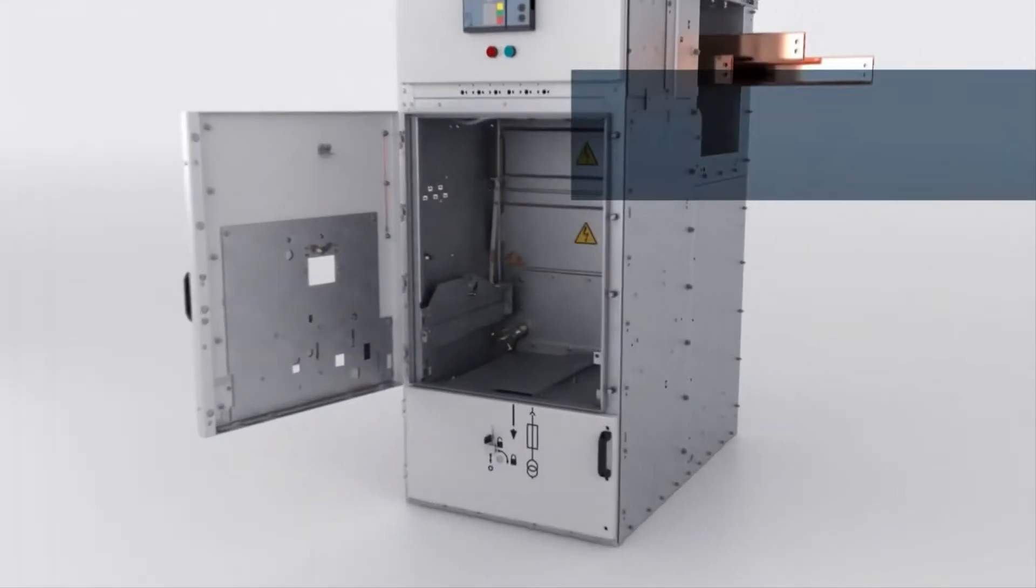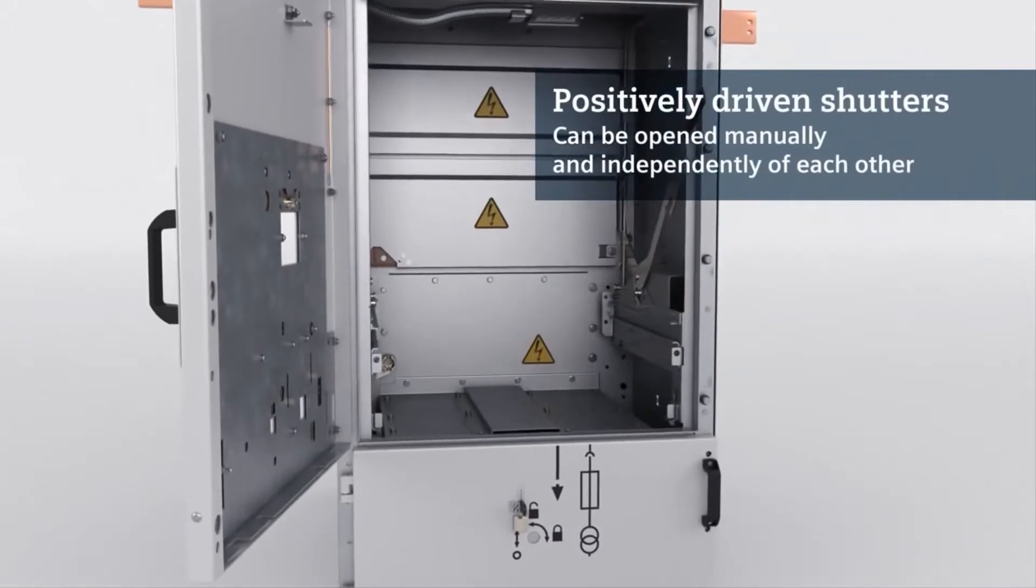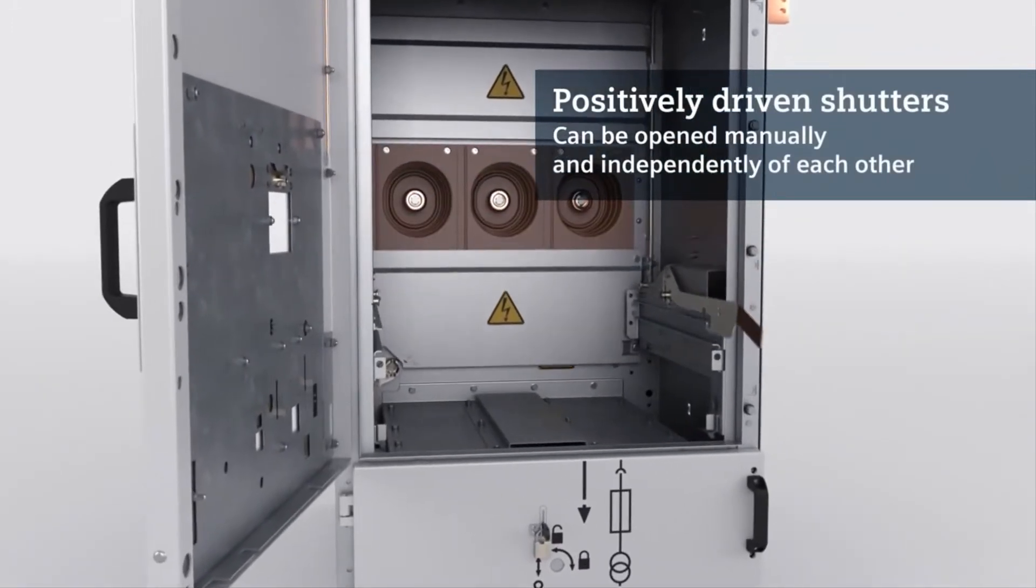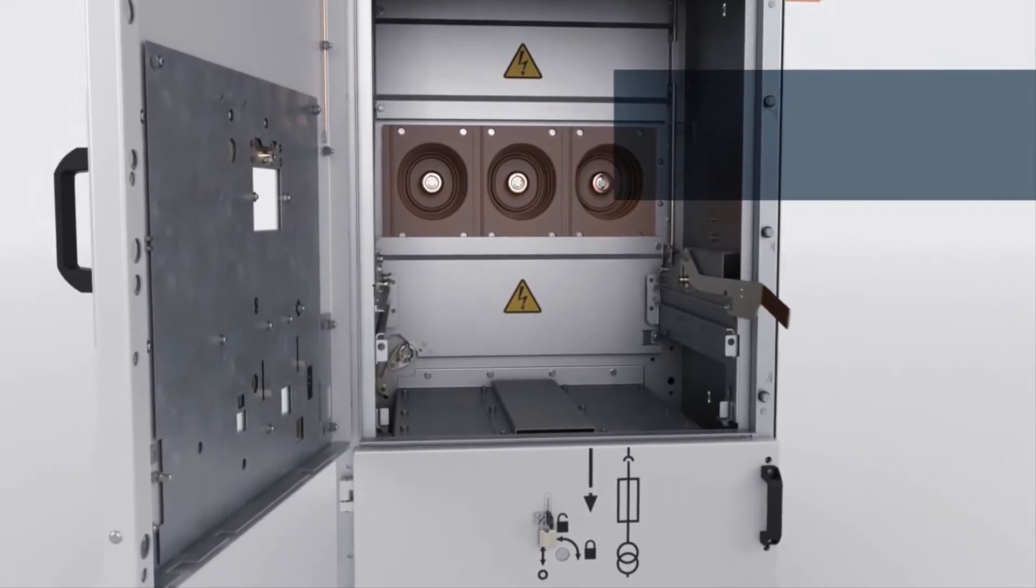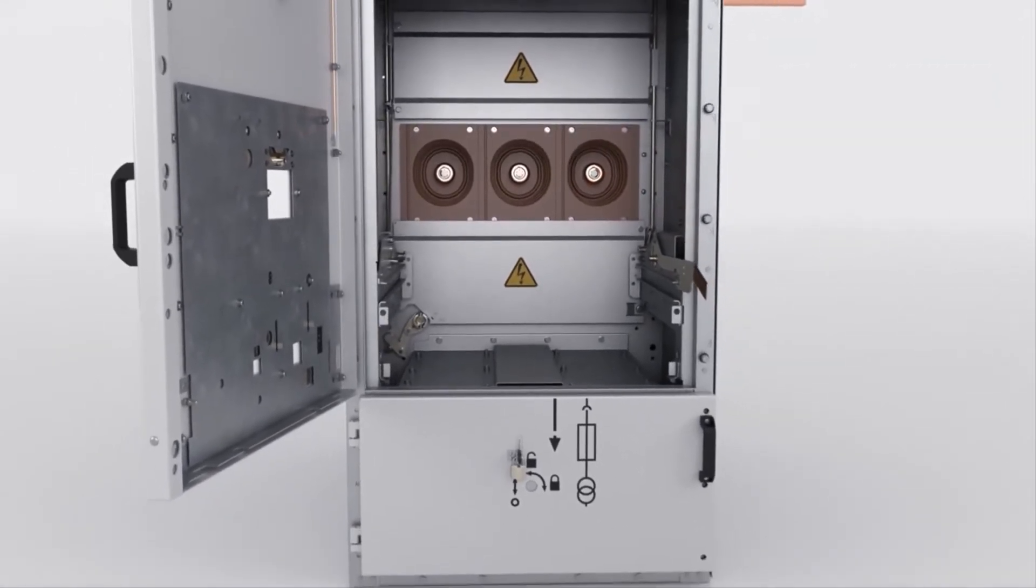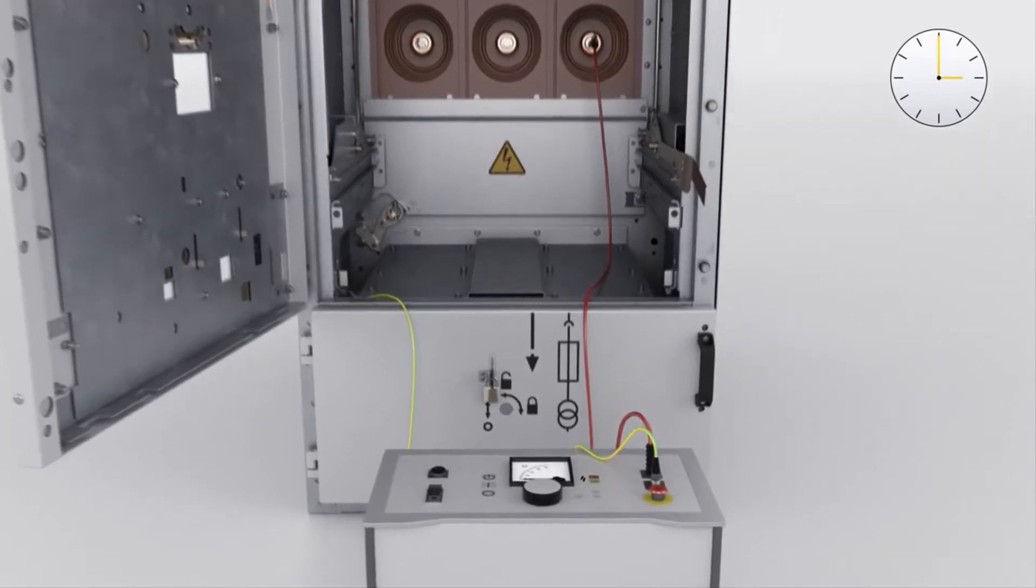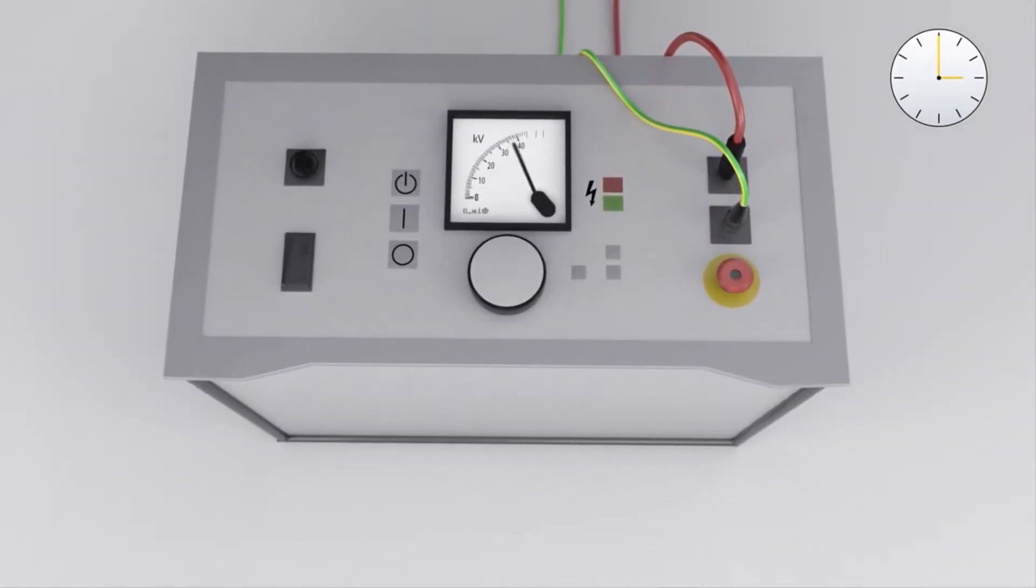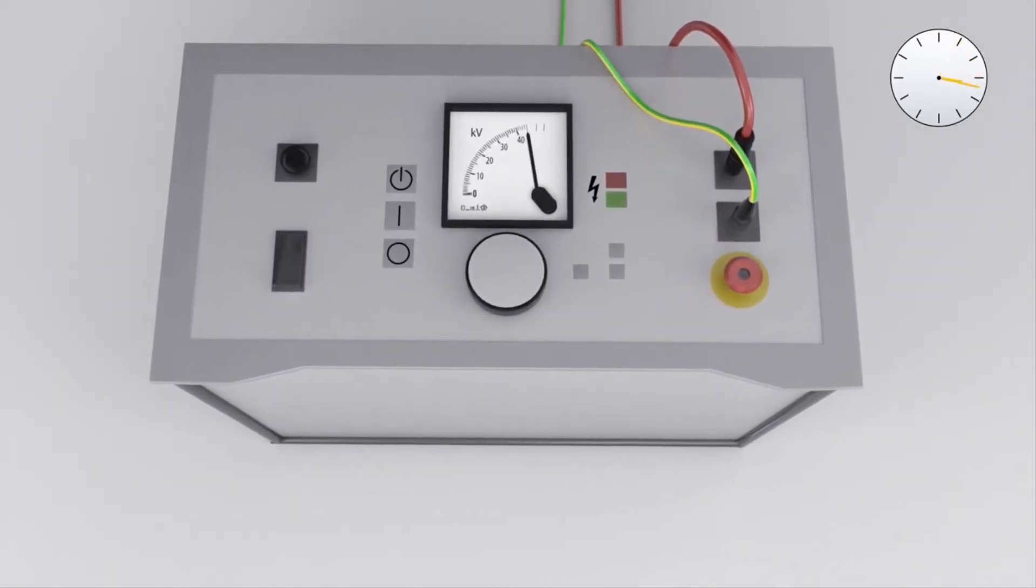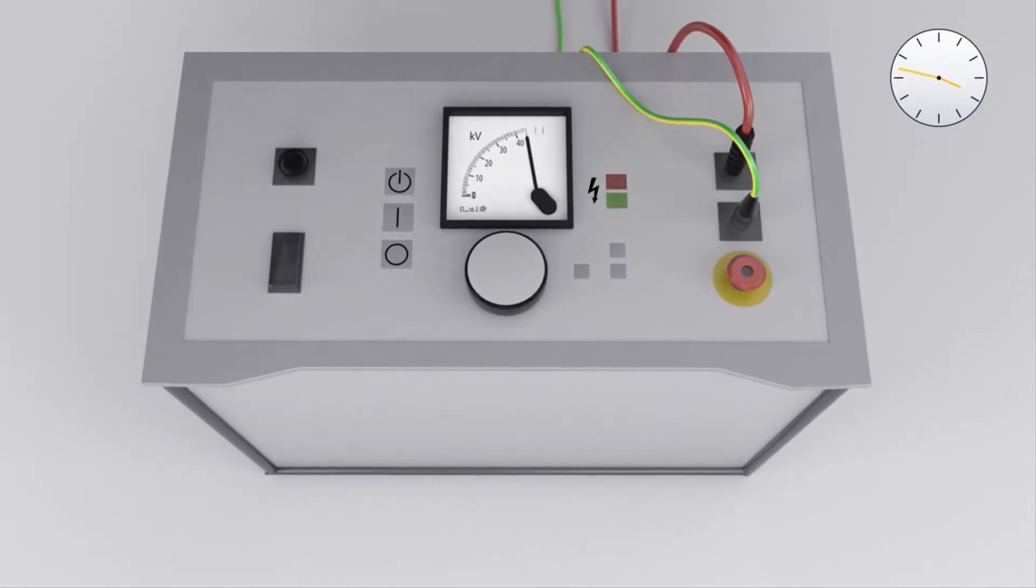The positively driven shutters are closed; however, they can be opened manually and independently of each other. The upper shutter stays closed when the lower shutter is opened for a cable test. The bus bar is thus covered and touch-safe. The repaired cable can undergo a dielectric test without dismantling the primary cable termination and without isolating the bus bar.